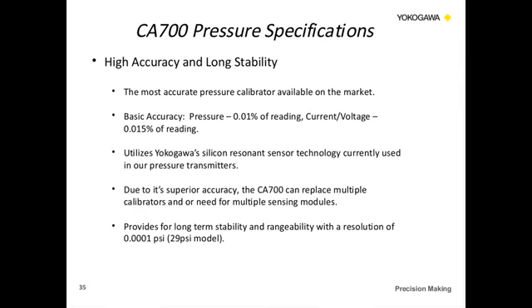So we talked about the CA700 being the most accurate on the market, and as far as the specification is concerned, the unit itself has a basic accuracy of 0.01% of reading. And this is really an important point, because we are the only manufacturer that lists the accuracy as a percentage of reading. Most manufacturers list it as a percentage of the span. So depending on the actual span, and we'll talk about this in the next slide, there's a tremendous difference when you talk about the accuracy over the entire span of the unit.